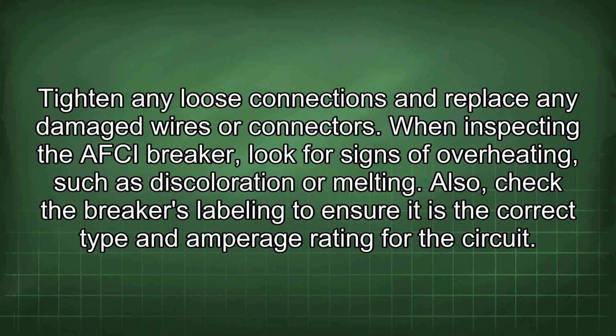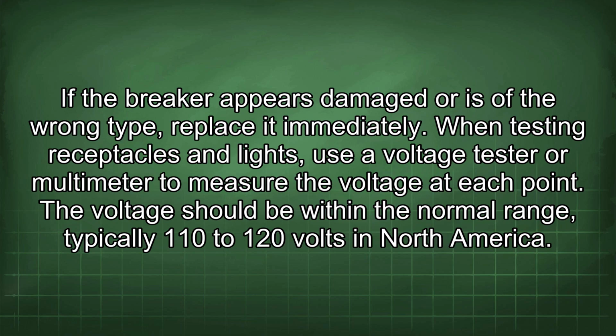When inspecting the AFCI breaker, look for signs of overheating, such as discoloration or melting. Also, check the breaker's labeling to ensure it is the correct type and amperage rating for the circuit. If the breaker appears damaged or is of the wrong type, replace it immediately.